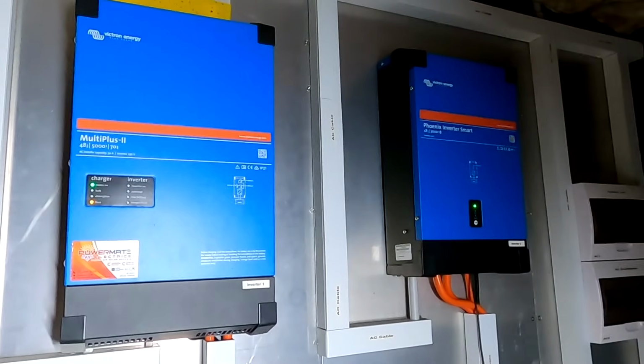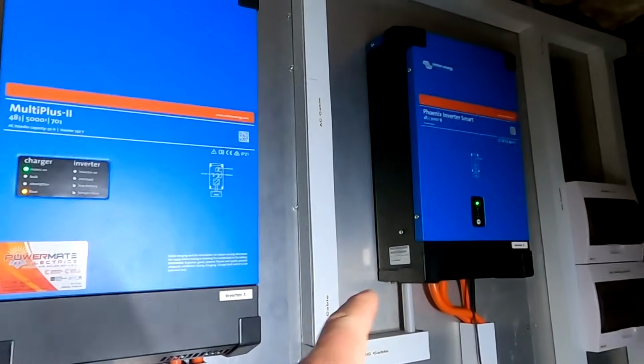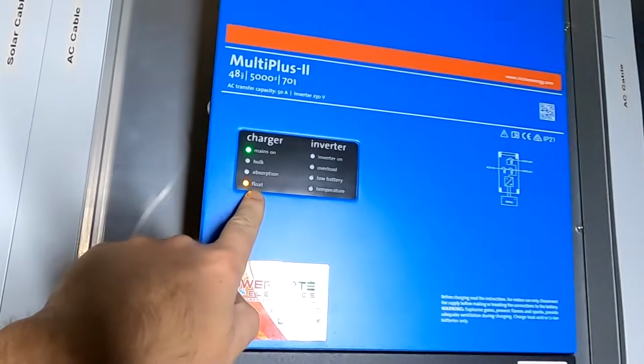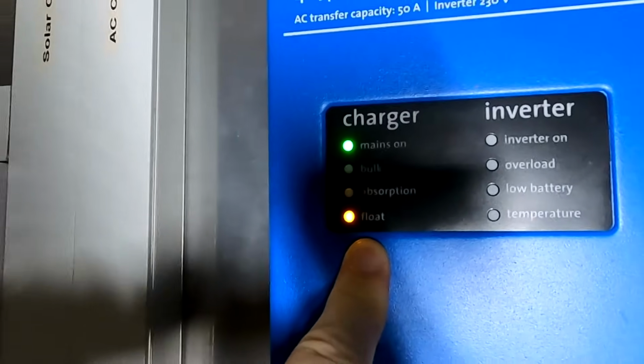So my friends, it is a bit later than anticipated, but the generator is still running and the Multiplus is on float mode. I have set the float voltage the same as the absorption voltage in the Multiplus, so we keep the battery constant at 56.8 volts, just for the test.